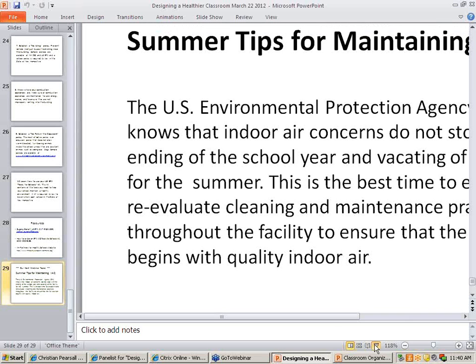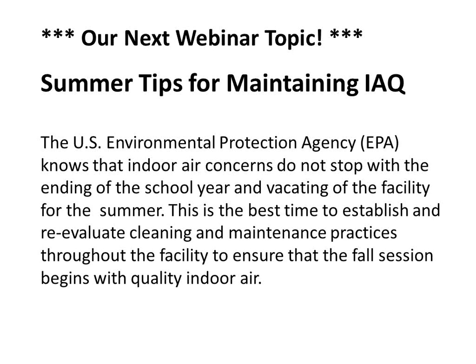This question comes out of the North Country. The question was, how do you measure the airflow in the classroom? If I'm a school, how would I judge the airflow? Is there a way to do that on their own? Well, there is a very sophisticated way. You can use a ventilation flow hood, which is a device that goes over the diffuser, and it can actually measure how much air is coming out of that particular diffuser.